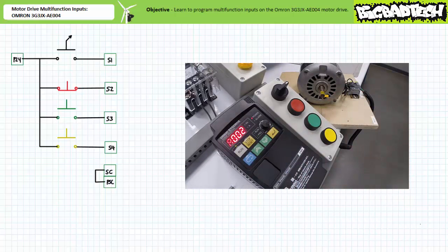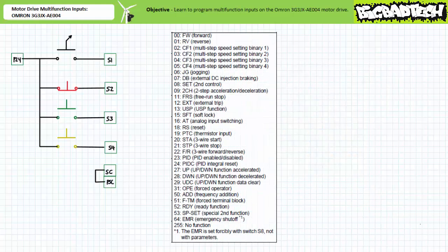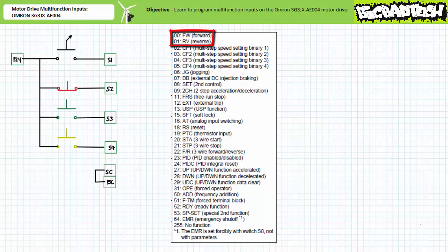Each input has a truly dizzying range of functions that can be assigned to it, including but not limited to forward, reverse, three wire stop, three wire start, reset, jog, forward/reverse selection, external trip, and more. Since this could get out of hand rather quickly given the numerous options available to us, let's restrict our analysis to a very small set — namely 00 forward and 01 reverse. Let's first make use of only a single input.